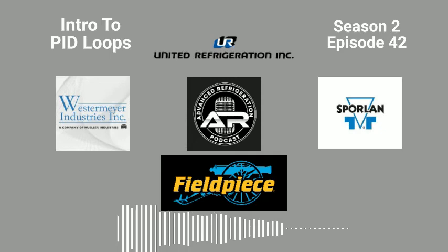So it looks at, okay, this set point, it's drifting away. The set point's 20, it's at 25. Okay, well, we added P to it. It's not coming down. Now we're going to add I. I adds over time. Every time the loop runs, it's going to add I. What I ends up doing is smoothing out the mountains.